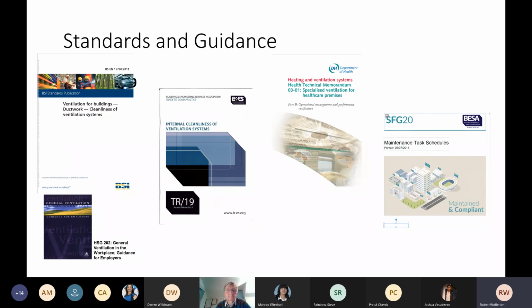So that's where BS 15780 came in, and I'll come on later in the presentation to what that really covered in terms of pre-commission ductwork systems, because essentially you were having large hospitals, in some instances, handed over to the NHS, educational establishments with a contaminated ventilation system with builder's dust, which is notorious for getting into ductwork systems. So BS 15780 really hit that on the head and tried to stamp that out within the industry.